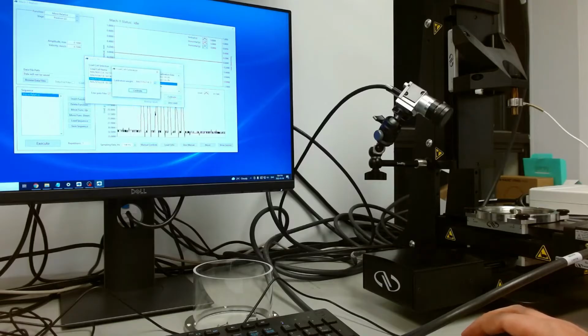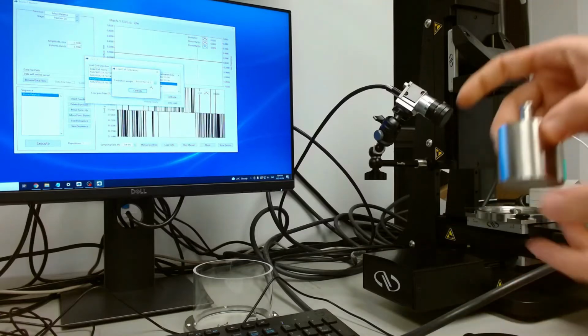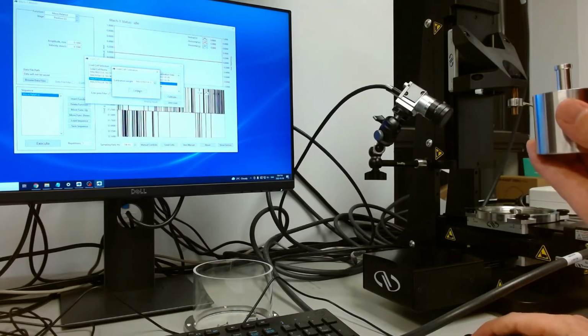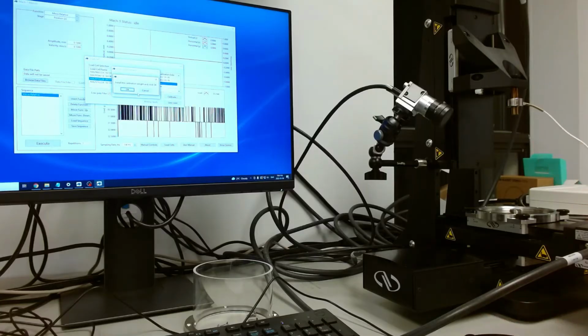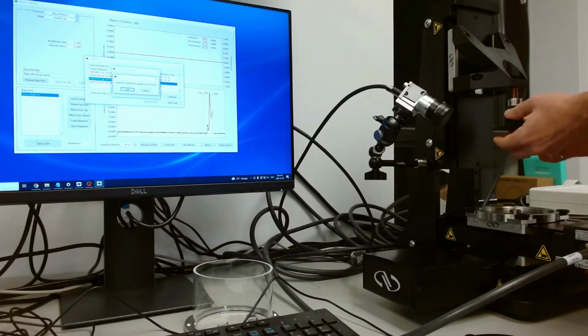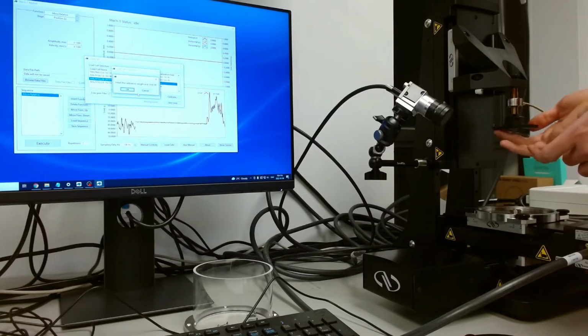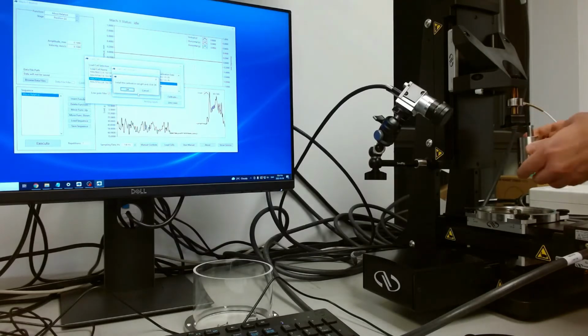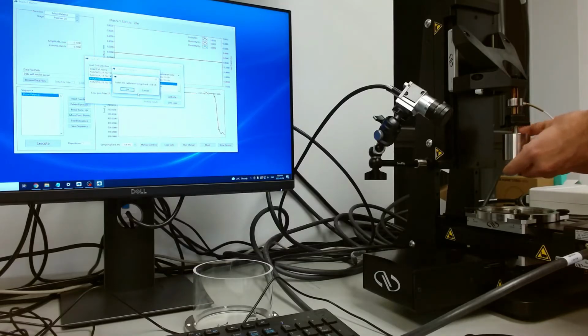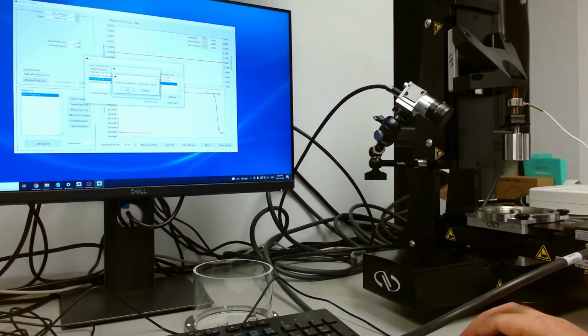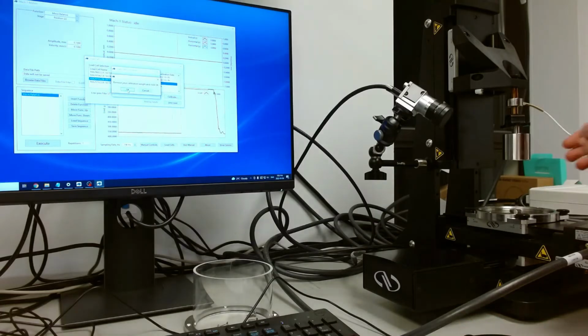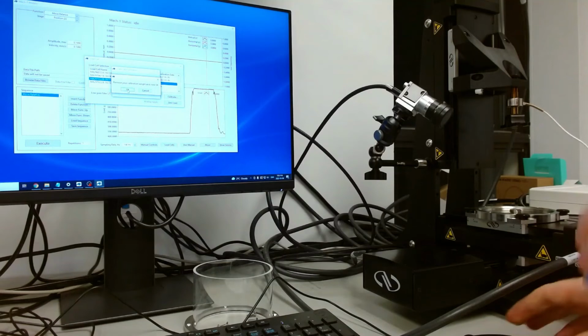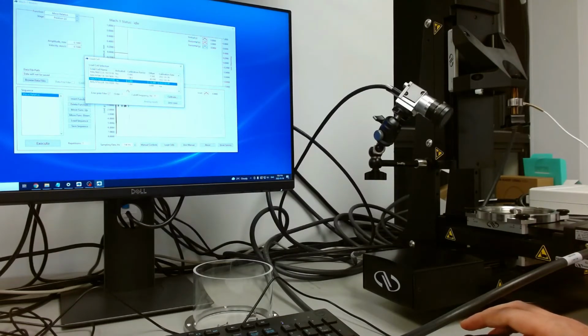Final check would be to perform a calibration by selecting the proper weight. So in this case, I only have one weight of around 500 grams. Clicking the calibrate button, the instructions are install the calibration weight and click OK. What I'll do, install the calibration weight holder, always using very light touch to do this. Placing the weight into the holder center, clicking OK on install the calibration weight, removing only the weight, and then clicking OK on remove the weight.